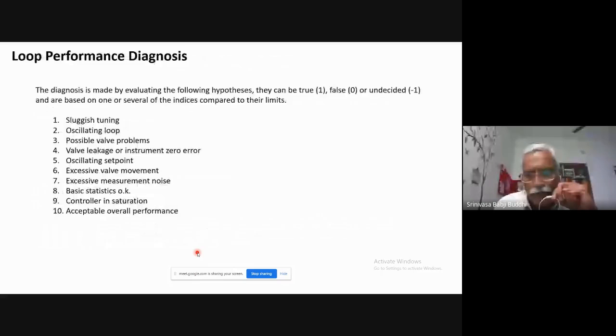Okay. So once you calculate these indices, then we have various hypotheses here actually. For example, we have hypotheses such as sluggish tuning, oscillating loop, possible valve problems, valve leakage, oscillating set point, excess valve movement, excess noise. Like this, we have different types of assumptions or hypotheses. Now, based on the indices or computations that were calculated, we have certain limits for each of those diagrams and calculations that we do for various indices. Based on the limits, if it's more than that limit, then we say that that particular index value is more than the limit. So that is used in the evaluation of these hypotheses.